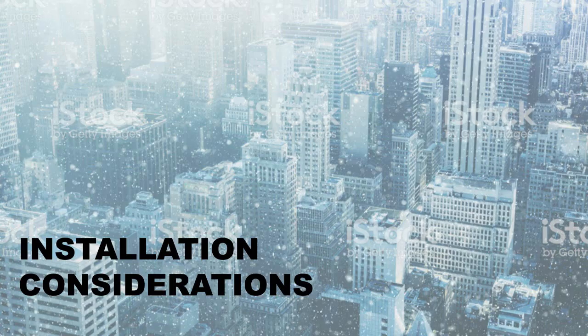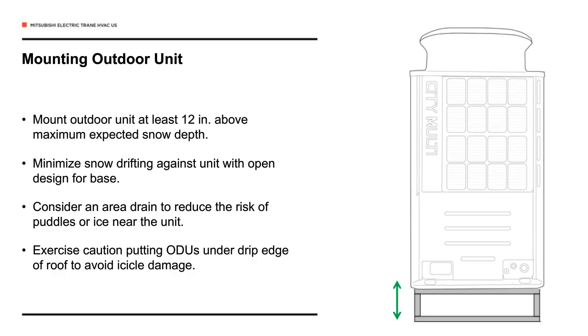So a few other installation considerations. We always want to get the condensing units or outdoor units mounted up off the ground on an open stand. Typically, we want this to be at least about 12 inches above whatever you expect the snow depth to be. 18 inches is kind of a common height that we see. You want to make sure it's open so that snow doesn't drift against it. The snow would just blow right through with the open stand.